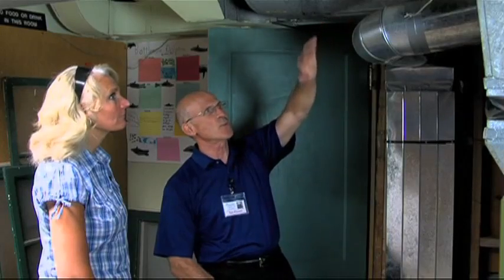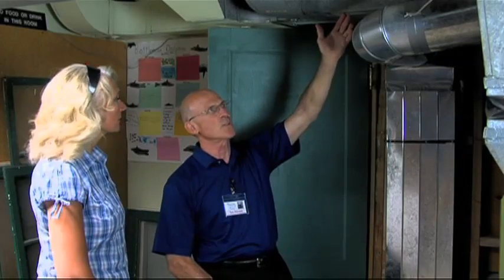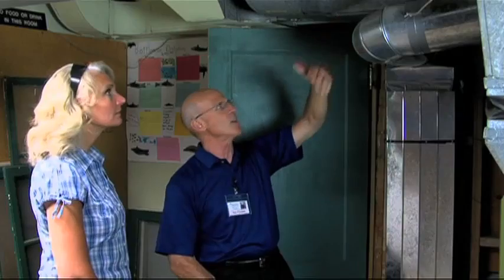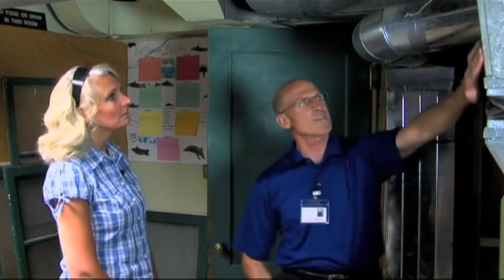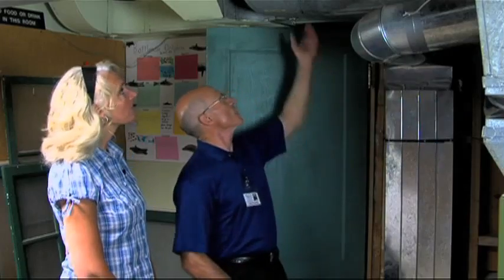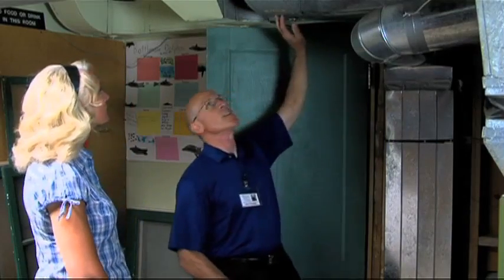Well, at first glance here, the ductwork is pretty good. Back in the day, this was craftsmanship type work. You see how the turns are gradual there. That provides for more even temperatures and quietness. You can tell from the craftsmanship here that you even have a dampering system right here that helped balance the heating to the different rooms, so that helps make the rooms more comfortable.